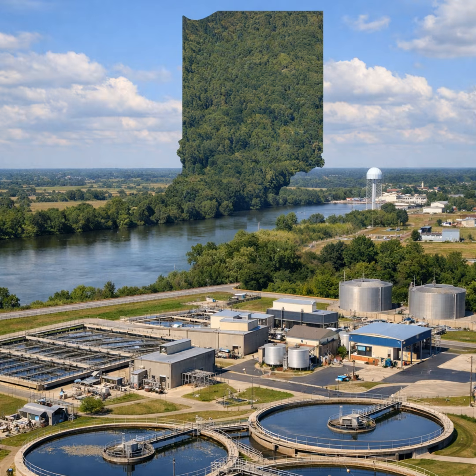It's just fed in different stages throughout the tank. A complete mix is the next thing, and that is characterized by the introduction of influent wastewater and return activated sludge throughout the aeration basin and use of a completely mixed aeration tank. So a complete mix is just completely mixed throughout the tank.